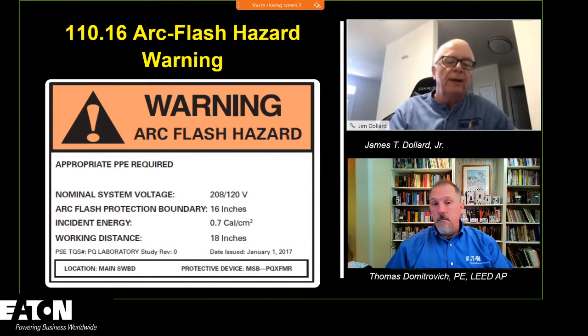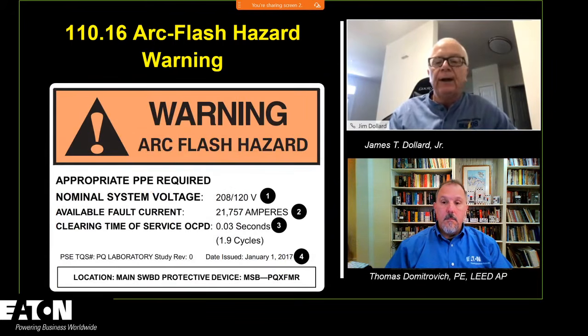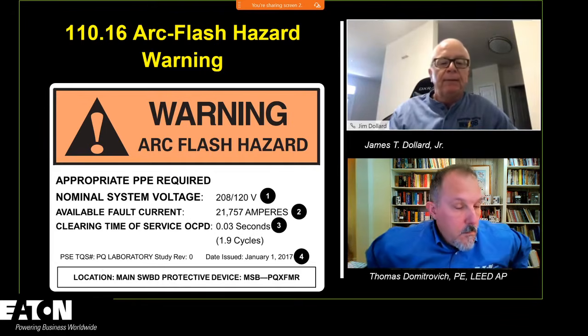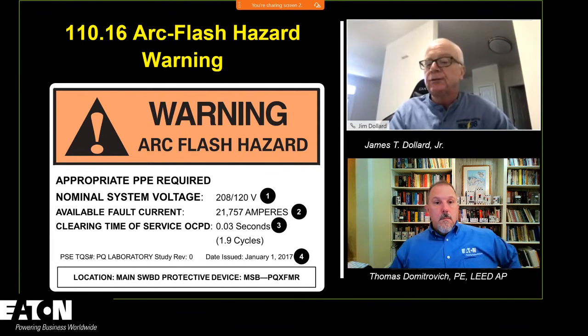If you go back one slide, what you'll see is that the NEC requires the fault current and the clearing time. That's not as useful to somebody picking PPE, but it was the only way for us to get where we needed to be, to build an exception that drove you to 70E.